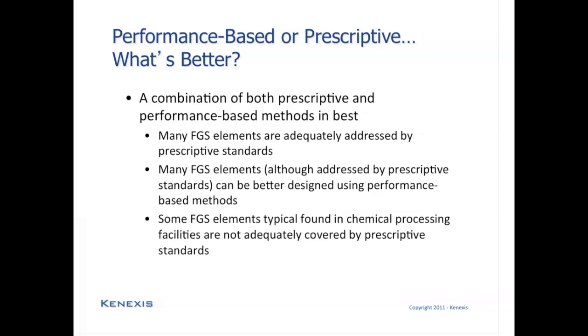Many of the fire and gas system elements are going to be adequately addressed by the prescriptive standards. And using prescriptive standards is going to give you a very rigorous design, and it's going to be very effective and very quick, whereas the performance-based standards are going to be a lot more time-consuming and require a lot more analysis. So if some of the fire and gas system elements can be addressed using prescriptive standards, that is the quicker and more effective way to go.